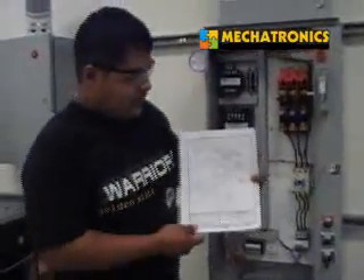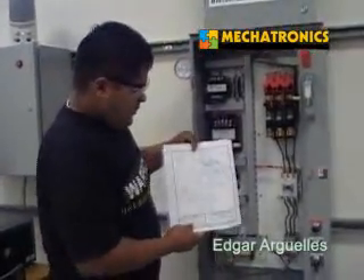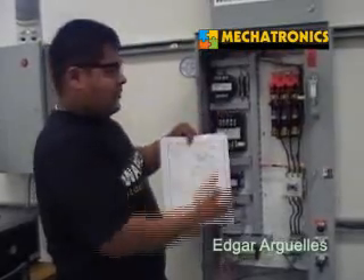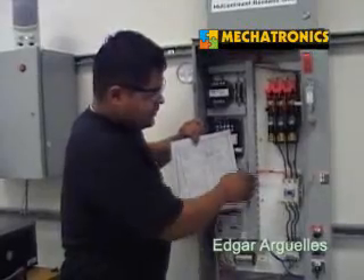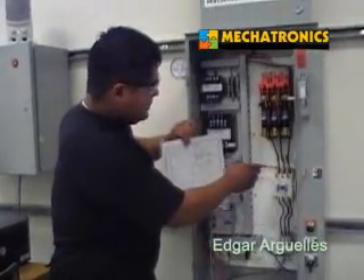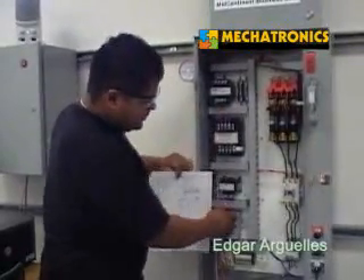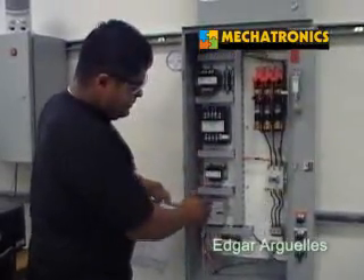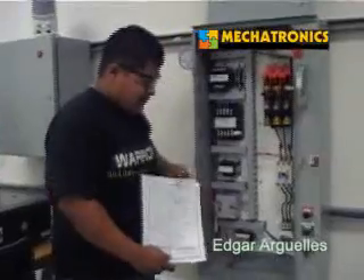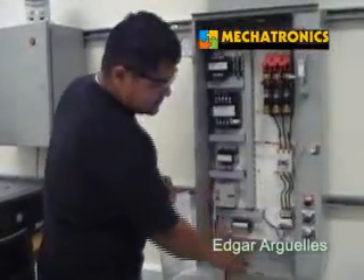I'm Edgar Arguelles, and here's the schematic that Chevron gave us — me and my teammates wired it. Right here we have the fuses that will have 220 volts. From there it goes down to the contactor, and from there to the overload. From the contactor we get to the suppressor, which goes to the transformer, and that's going to drop the voltage from 220 to 120 so it can work, because the PLC needs 120 to work. From that transformer we drop it down to 120 to work the PLC, the push buttons, and turn on the motor.